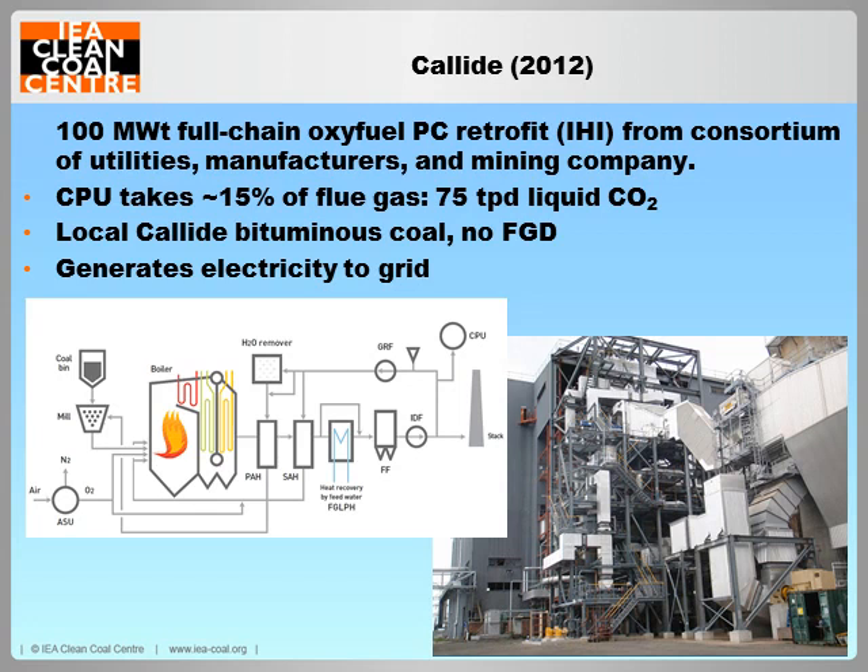The current pacesetter for oxy-fuel pilot testing is found here in Australia at the Callide A power plant in Queensland, where a 100 megawatt thermal unit has been commissioned by a consortium of companies with support from the governments of Australia, Japan and Queensland. Besides being by far the largest oxy-fuel unit operational, the plant is notable for being the first boiler retrofit and the first to generate electricity to the grid. Furthermore, the lack of FGD in the plant means that the CPU is obliged to deal with relatively high concentrations of SOx in the flue gas. Successful commissioning in 2012 has been followed by improvements in management of corrosion, sealing and plant process logic, and test campaigns will include high temperature corrosion studies and the effect of varying CO2 concentration on the CPU.